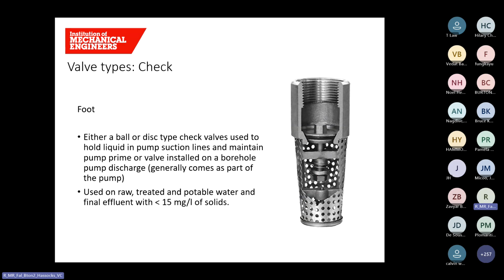The foot valve is a check valve which is immersed in water and is usually used to maintain the prime of a pump. So where the pump is located above the water line and water wants to travel back into the well, this valve will prevent that. Sometimes they're installed on borehole pumps, in which case they come as part of the pump, and sometimes they're separate from the pump. They tend to be used on raw water, treated water or potable water applications, and possibly final effluent which doesn't contain any rag.